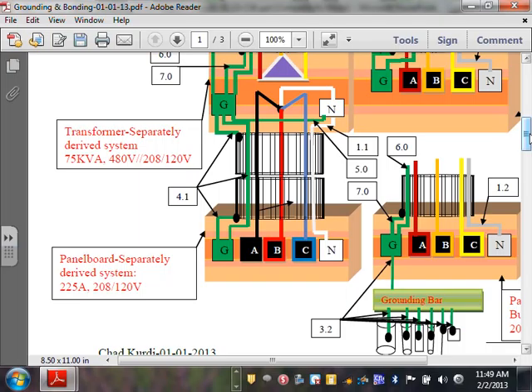So this is typically for any transformer, 480, 277, or 600, 208, anytime you have a created neutral. Anytime you create a neutral. Any comments?